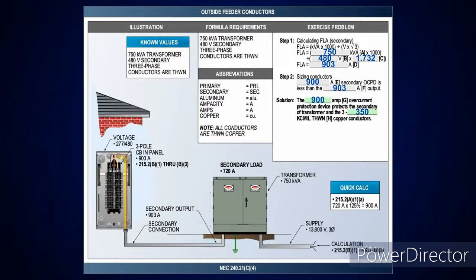But what we like to point out here is make sure you know the sizing of your overcurrent devices and how you do it on the application of 240.4B and 240.4C. So once you see it's over 800 amps, you need to start looking at how high it's going up, because you need to drop down at that point.